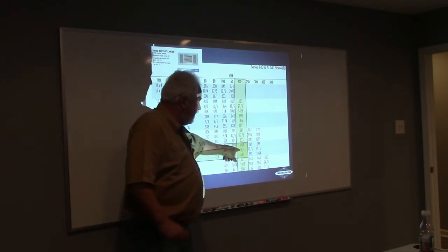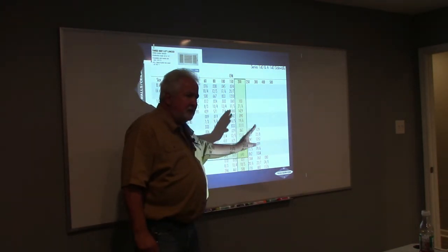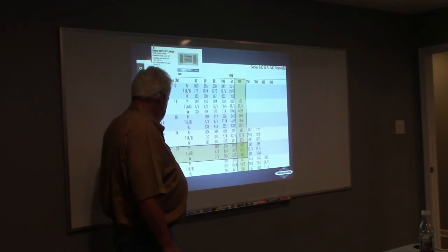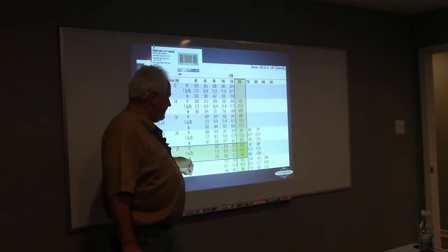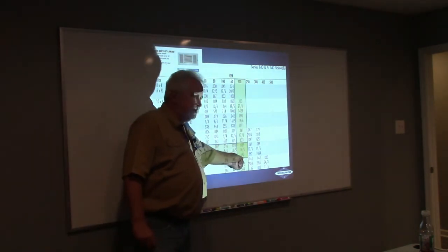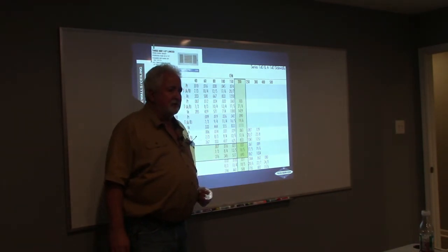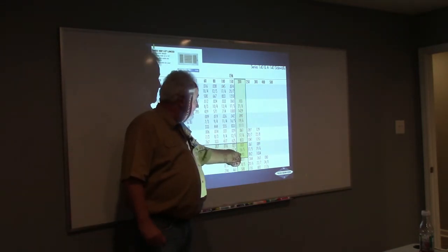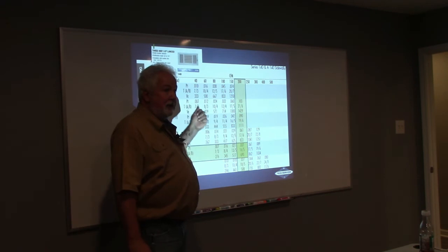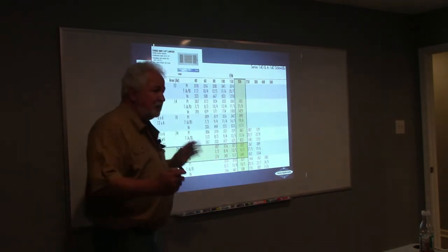Okay, so we're kind of close right there, but we're still probably a little bit farther than we want to be. What's the velocity of this? It's too high. So would this be the right grill for our application? Probably not. We're not going to use that.